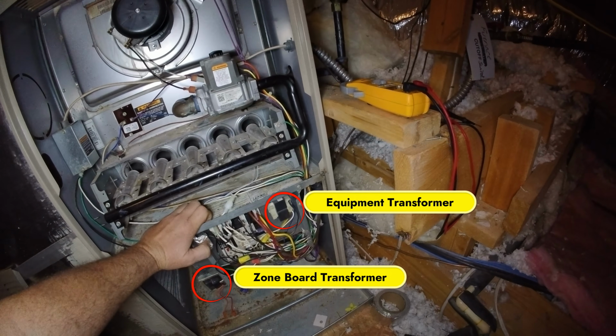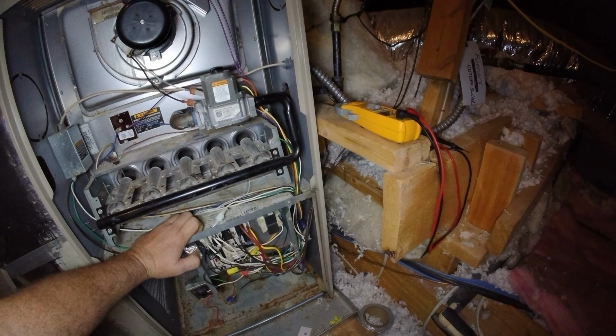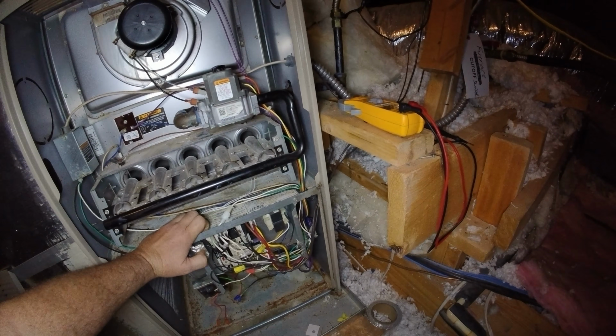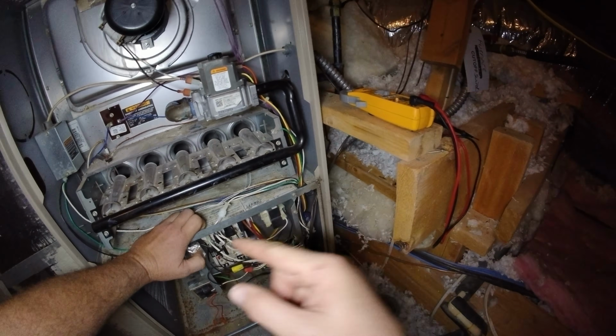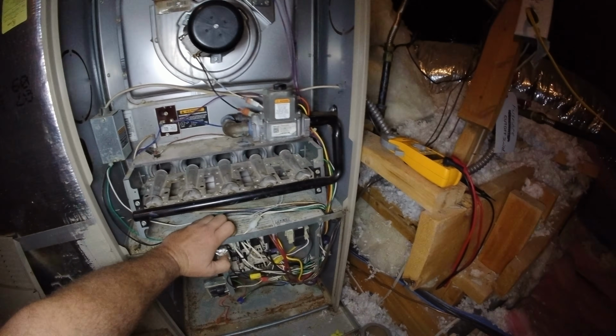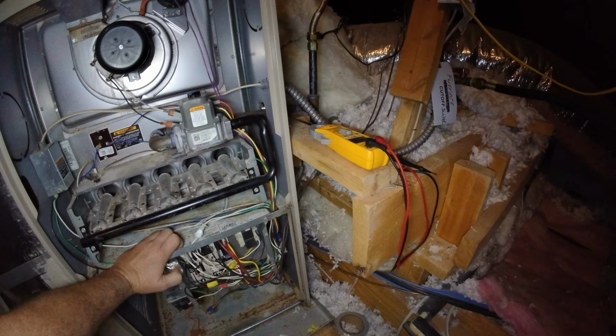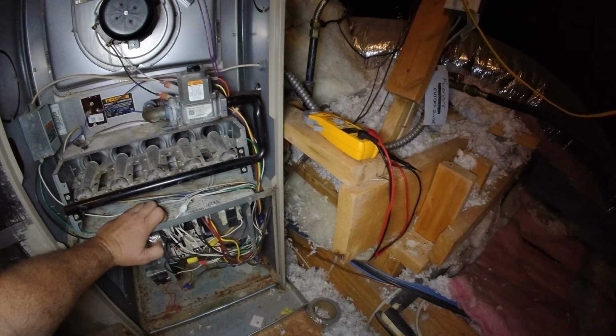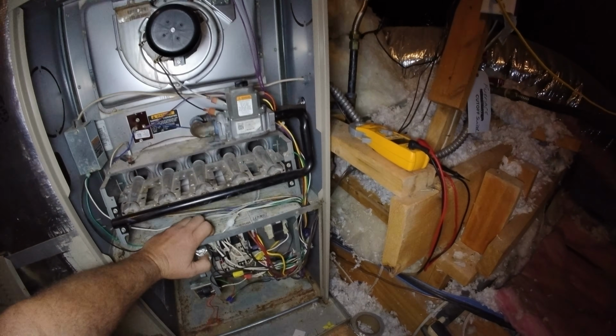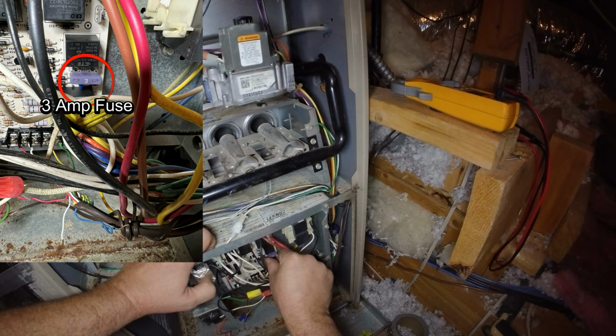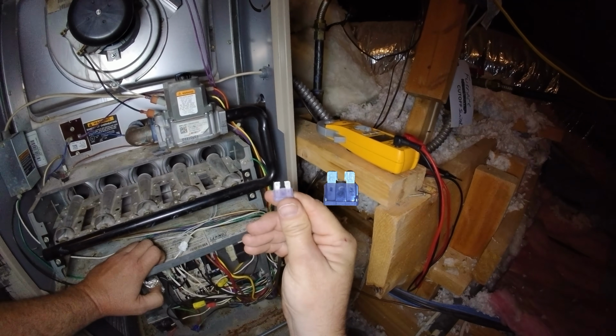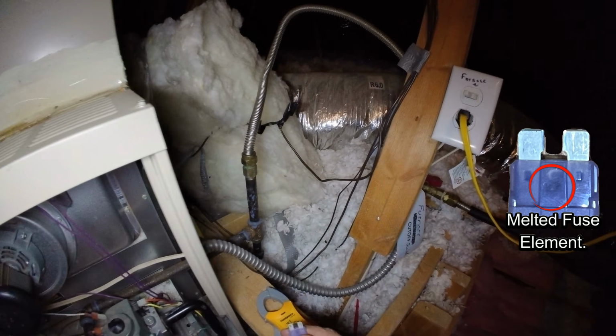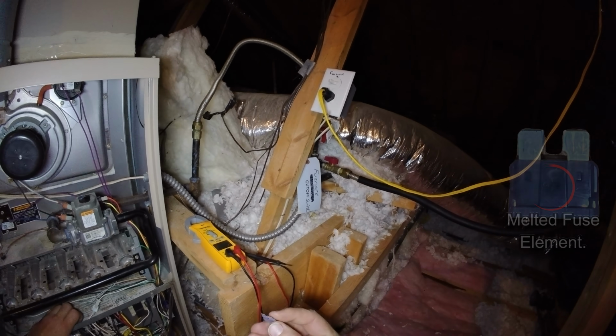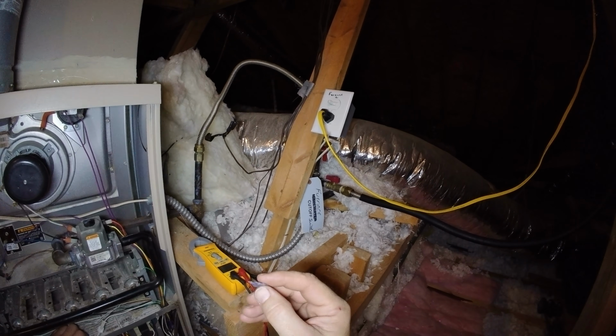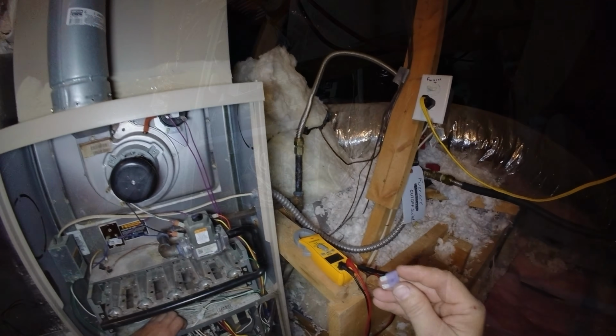but we're not getting 24 volts to our board itself. So in these particular cases with zone boards, some of them, well, they all should really generally have their own transformer for the board and for the unit. However, in some cases that won't happen, and they'll just wire in one transformer to run both. But you won't usually have the volt amps to be able to do that, so it's usually a better idea to put in a secondary transformer. But we have a blown fuse here, and whether that's just a nuisance trip or a different kind of issue with a short somewhere, we'll have to dig into and find out.